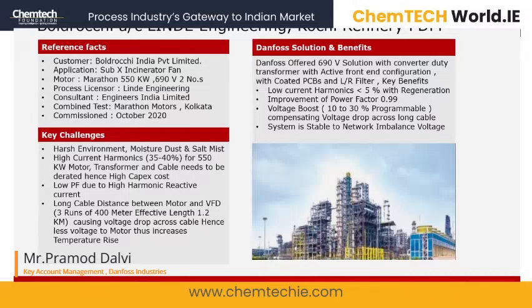And this active front-end configuration has enabled us to give low current harmonics below 5%, compared to 35 to 40% if we would have used a standard 6-pulse. Now with this solution, it has gone below 5%. So definitely the transformer and cable derating has decreased. The power factor has been improved to 0.99, whereas otherwise it would have been in the range of 0.84 or 0.85. For a 550 kilowatt motor, this is very, very low, and there is definitely a loss of energy in efficiency.